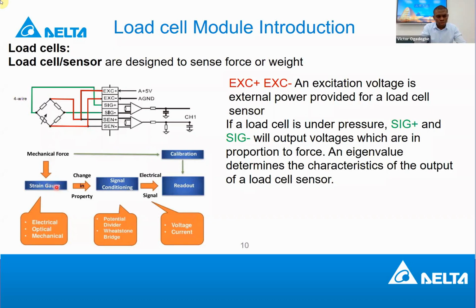It's a strain gauge. If you apply mechanical force on it, there will be a change in the resistance. That change in resistance will produce an electrical signal in millivolts, a very small voltage. Then there's some form of amplification circuit, in this case with a bridge. This circuit amplifies the small voltage and gives you an output voltage that corresponds to the mechanical force you have applied. This output voltage varies from sensor to sensor.